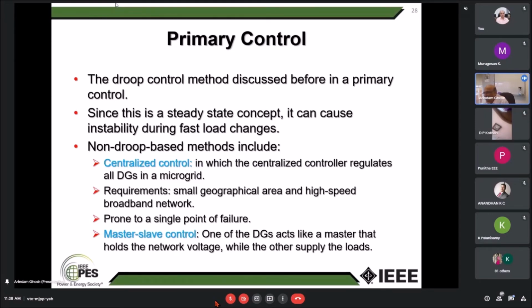Now there are non-Droop based control methods that include a centralized controller. For example, if I am setting up a microgrid in IIT Madras, what's the area? Not very big. So I can have underground broadband cable everywhere. I have load centers, I can measure their voltage and angle, because these days it's very easy. Just put a microprocessor, all you need is a synchronizing signal, and I can have a phasor measurement unit. So I can measure the voltage and angle and current and angle in every bus.